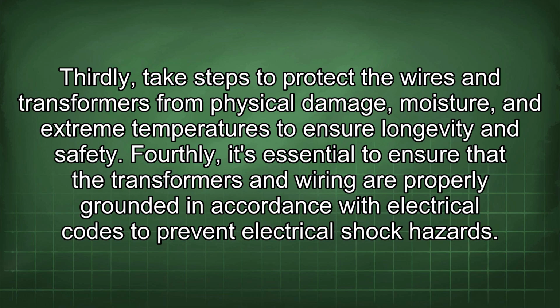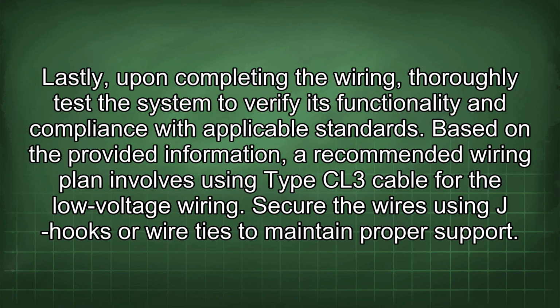Fourthly, it's essential to ensure that the transformers and wiring are properly grounded in accordance with electrical codes to prevent electrical shock hazards. Lastly, upon completing the wiring, thoroughly test the system to verify its functionality and compliance with applicable standards. Based on the provided information, a recommended wiring plan involves using Type CL3 cable for the low voltage wiring.